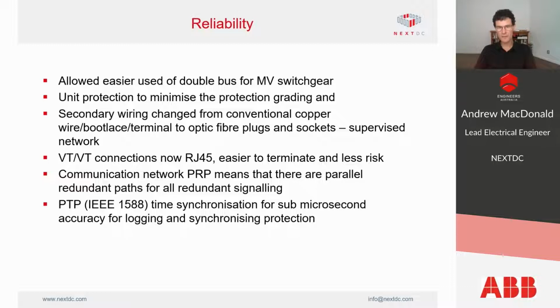So the reliability, the smaller sensors and the other advantages allowed us an easier use of a double bus for our medium voltage switchgear. That goes towards our reliability a lot. The unit protection, so we've got differential protection, so that minimised the amount of protection grading that we needed. And the secondary cabling has changed from conventional copper wire with the bootlace and terminal to optic fibre plugs and sockets on a supervised network. So you get a warning if one of the optic fibres comes out, and the network raises an alarm for our facility managers to go and check out.